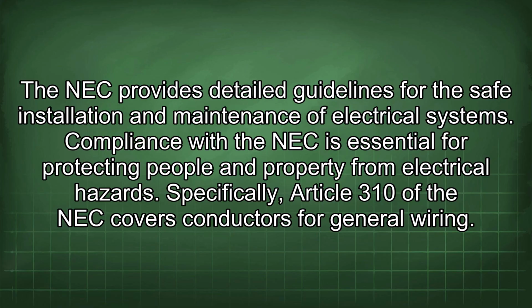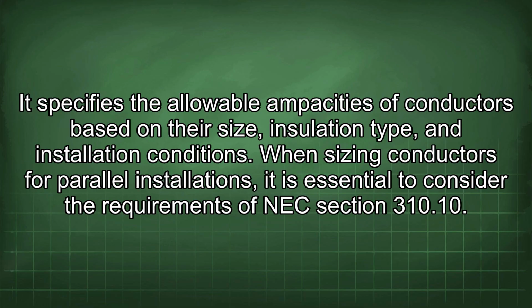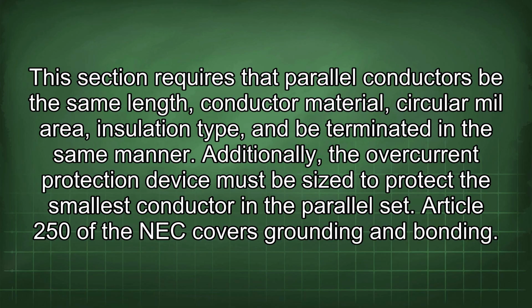Specifically, Article 310 of the NEC covers conductors for general wiring. It specifies the allowable ampacities of conductors based on their size, insulation type, and installation conditions. When sizing conductors for parallel installations, it is essential to consider the requirements of NEC Section 310.10. This section requires that parallel conductors be the same length, conductor material, circular mil area, insulation type, and be terminated in the same manner. Additionally, the overcurrent protection device must be sized to protect the smallest conductor in the parallel set. Article 250 of the NEC covers grounding and bonding.